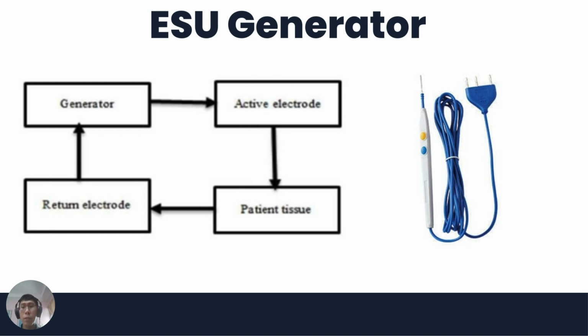An active electrode typically resembles a scalpel blade, and current density varies depending on the size and the shape of the tip. There are three main types of electrode tips: needle tip, blade tip, and ball tip. All are made out of stainless steel. The size and the shape of electrodes depend on the manufacturer and the intended use. In electrosurgical units, electrodes are categorized into two types: active electrodes and return electrodes. The active electrode is a flat blade electrode. The purpose is for cutting and coagulation.